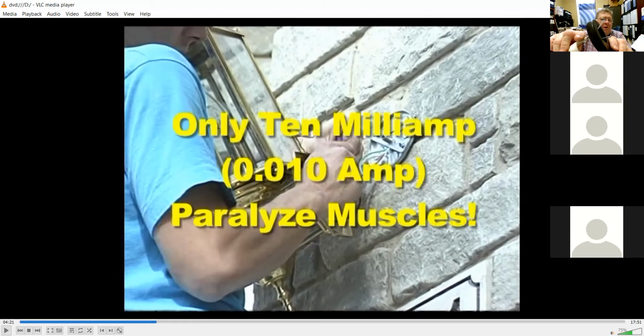What's the difference between 3 amps and 2.5 amps? Half an amp. So look, that current coil that's inside of that GFCI, it's a small one in there, but that current coil picks up that you've got a half an amp of difference between the amps in those two wires. And a half an amp is more than enough to trip that. Has everybody got that?